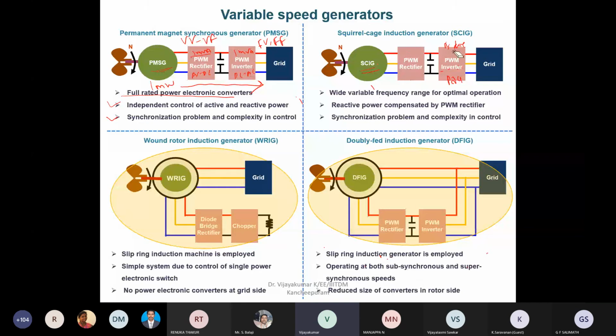Okay, now when we come to this same topology, the PWM converter is here. It will supply the reactive power requirement of this machine, and if I say it's a 1 megawatt machine, then 1 megawatt of real power it will supply through this converter itself. So here, if the machine rating is 1 megawatt, then I have to use 120% of the rating for the converters in the topology. That means I have to use 1.1 MVA, or we can say 1.2 MVA rating of the converter.